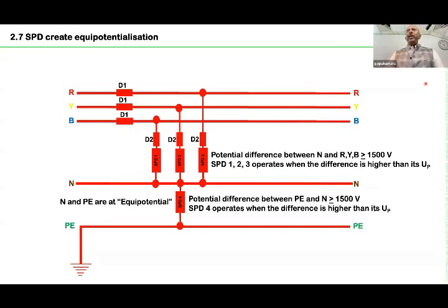Now, the SPD, which is in a shorted condition, also should come back to its original situation. After the passage of the surge, the transient current, it has to return to its original situation. If it didn't return, what will happen? Can anybody answer? If the SPD has worked, but it has created a kind of low resistive path between line and neutral, and it didn't return to its original position, that means you have a short circuit. So for the entire installation, you have to have a backup protection. Otherwise, the entire installation can catch fire.